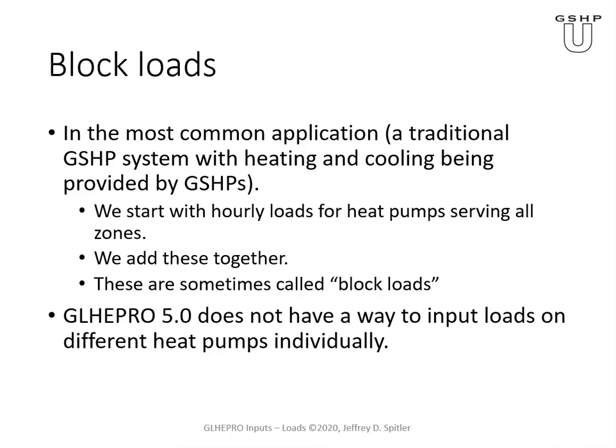I was trying to imagine users putting in each one of these sets of loads and specifying the heat pump for each one individually, and it deterred me from trying to incorporate that. All right, so that's why we take all the loads together, and they're all the ones, at least, that are going to be served by the same ground heat exchanger.